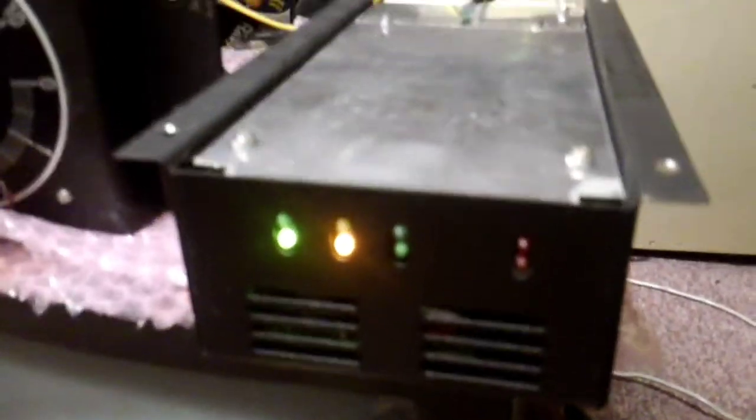So I'm at about 175 millitorr and this is how I'm going to activate the pump. Just plug in the variable transformer and you can see the yellow light is on indicating that it's accelerating.